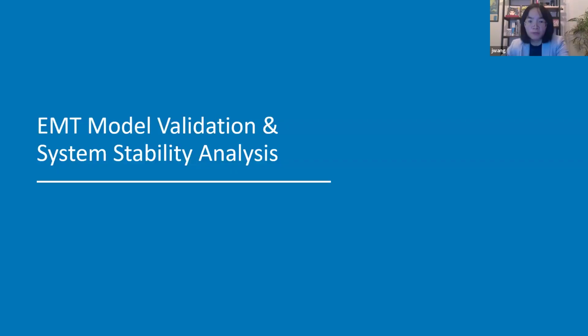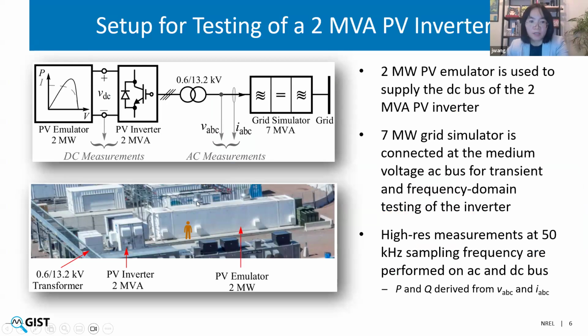Next, I will briefly talk about example results for the EMT model validation and the system stability analysis. This is performed by my colleague Xiayao. This diagram shows the setup for the 2 megawatt inverter. The bottom picture is the hardware setup, and the picture here shows the diagram. We have the PV emulator as a DC source, and then we have the vendor grid following inverter, the transformer, and also the grid simulator, with which we can apply a lot of different disturbances to do the test. We also have very high sampling, 50 kilohertz, to get all the voltage and current measurements and then do the processing. So this is the setup for the PV inverter model validation.